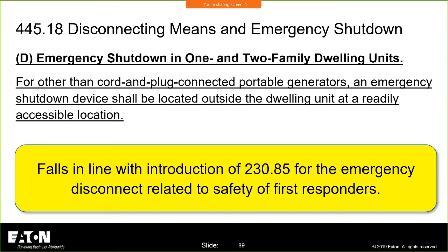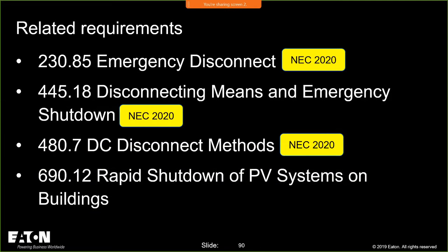This falls in line with the introduction of 230.85. That's the section where we had the requirement for the emergency disconnect, which I was lovingly calling the firefighter disconnect, which is there for first responders. And again, the other areas you're going to see, and we're going to cover 480.7 because there's a requirement there. And I threw in 690.12 because technically 690 was not a part of the firefighter disconnect discussion and code changes, but it does relate because the rapid shutdown is really there for the first responders and firefighters that have to get on that roof when these photovoltaic systems are installed on roofs. So you have a couple things that were already covered and a reason why we didn't have to make any changes to Article 690.